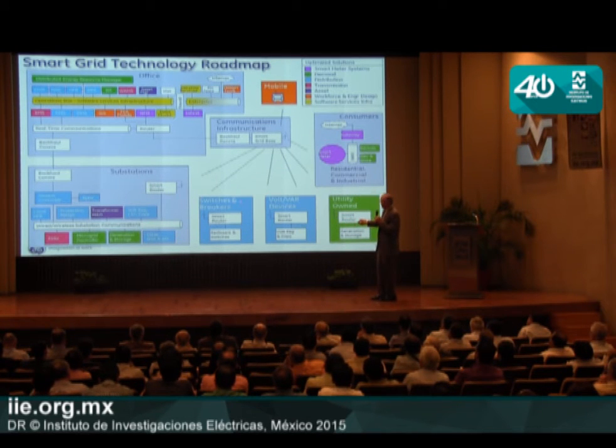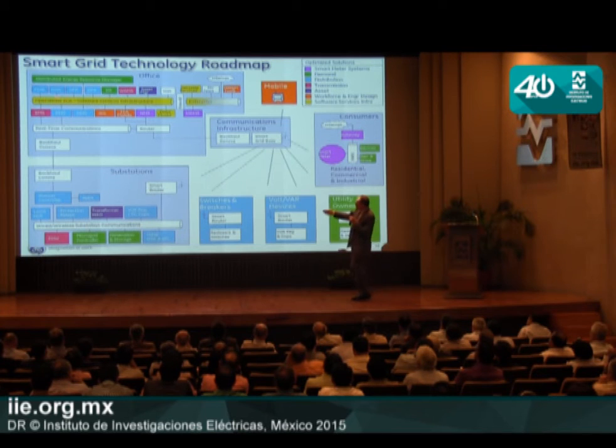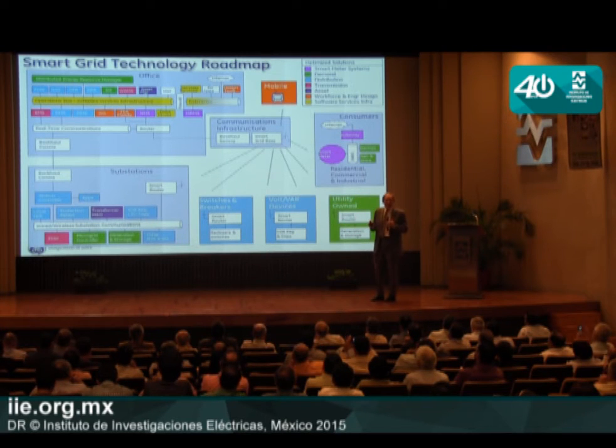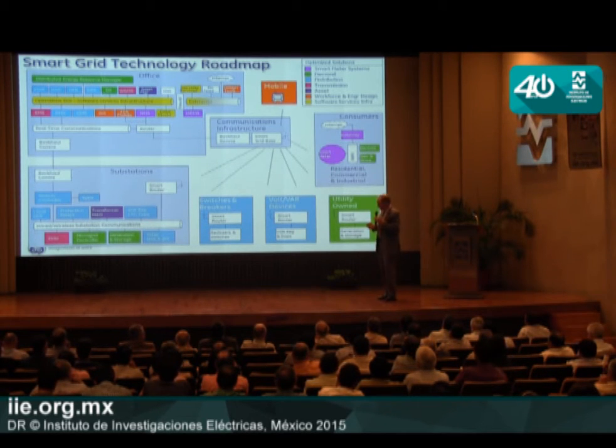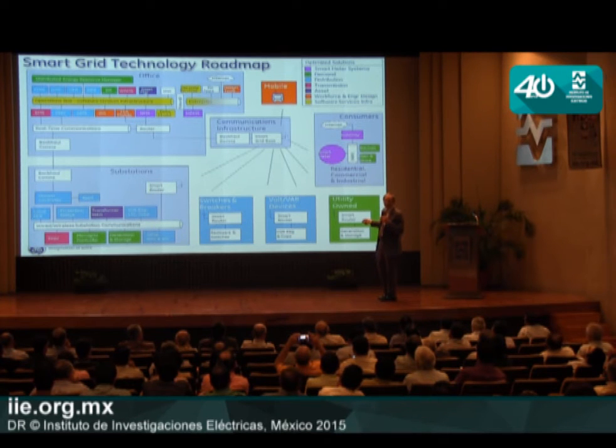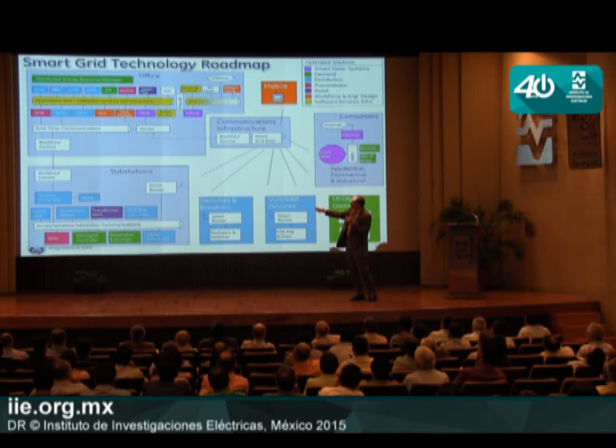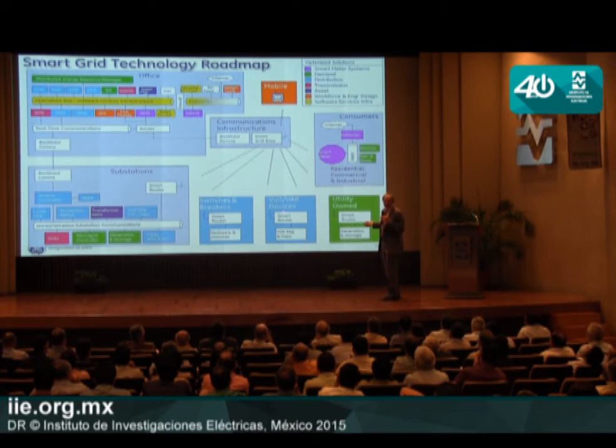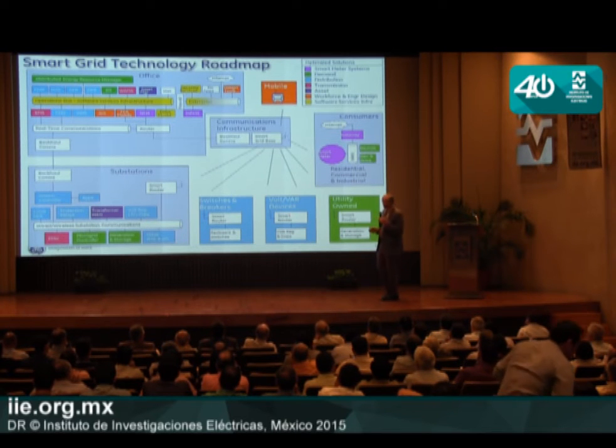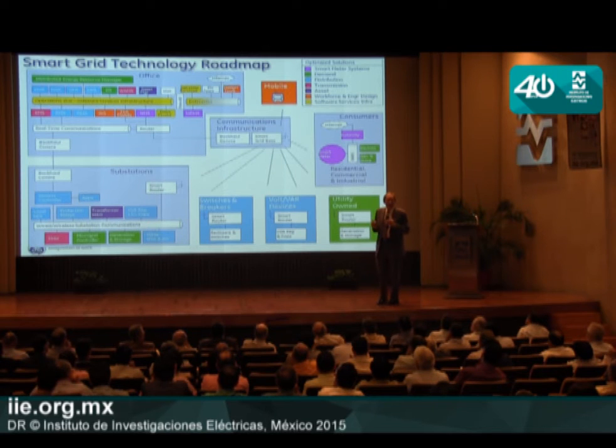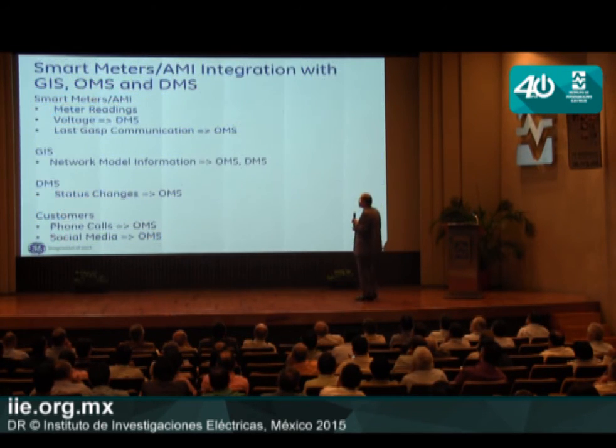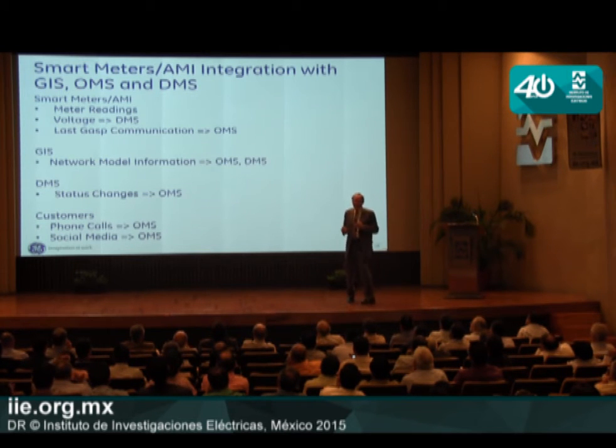Now we go outside the substation, and on the distribution feeders, we have switches and breakers. We have sectionalizing devices. We need these to support fault detection, isolation, restoration. When we detect a fault and we locate it, when we want to isolate it, right, we need switches or sectionalizing devices on each side of that fault so we can open them up and isolate the fault. Then we need volt-var devices, capacitor banks, voltage regulators to support integrated volt-var control. So this is the logic, and then this is the equipment out in the field and the smart controllers and the two-way communications. So think of it, it's not trivial to have all these light blue boxes from different vendors be able to interoperate, okay? So how can we make the grid more resilient?